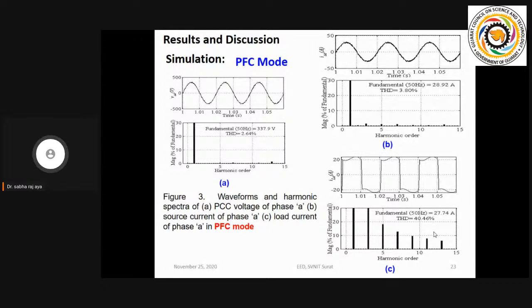After compensation, you can see the supply side current, how much? Supply side current is 28, distortion 3.8. Why did this increase? Due to some losses somewhere, or maybe due to LPF, maybe the LPF is not proper. After that, you can see the value of supply voltage distortion is near 5%. This is our requirement. Always we can maintain this value based on IEEE 519, in 2014 or maybe 1991, anyone can put.